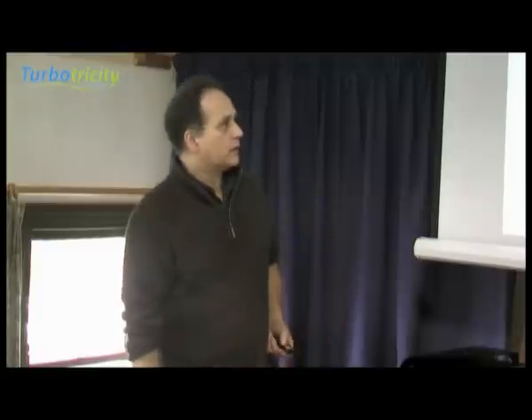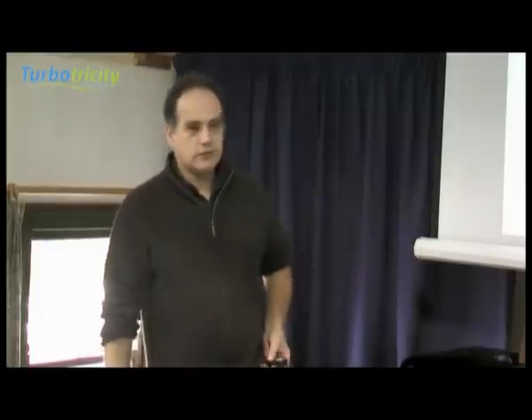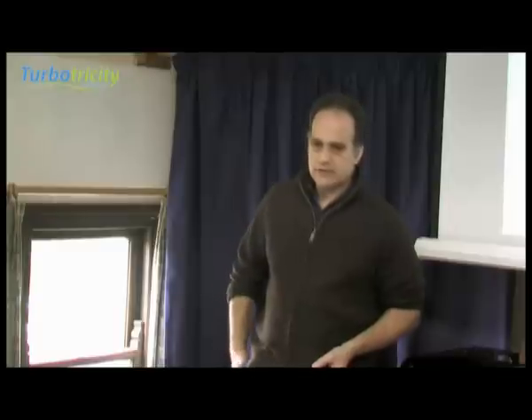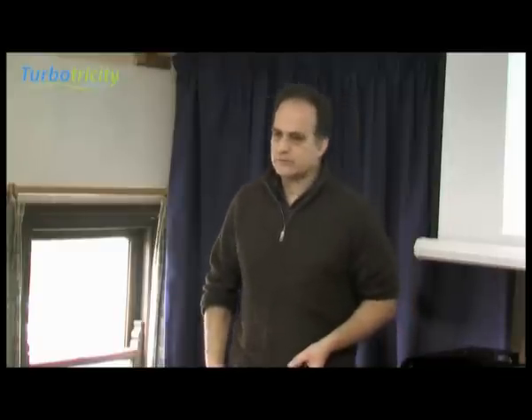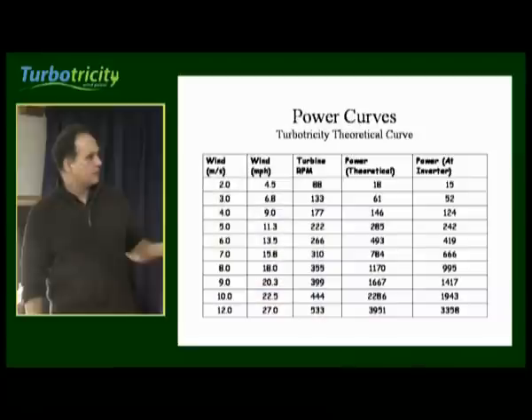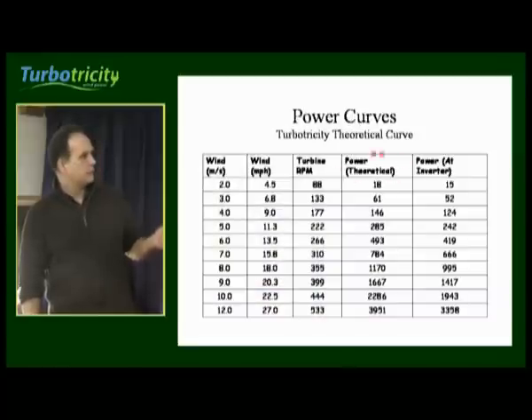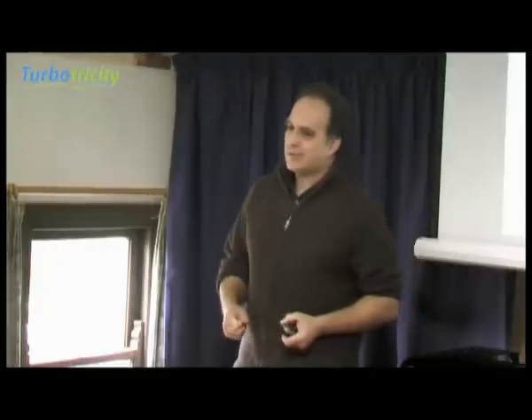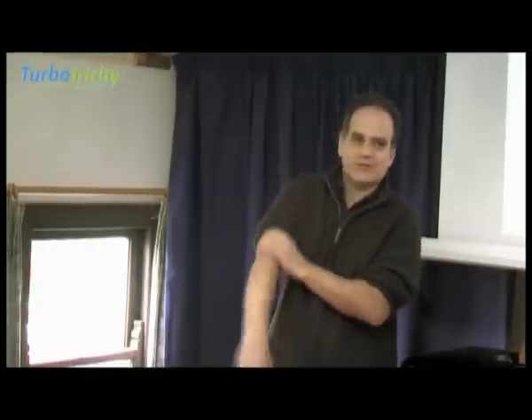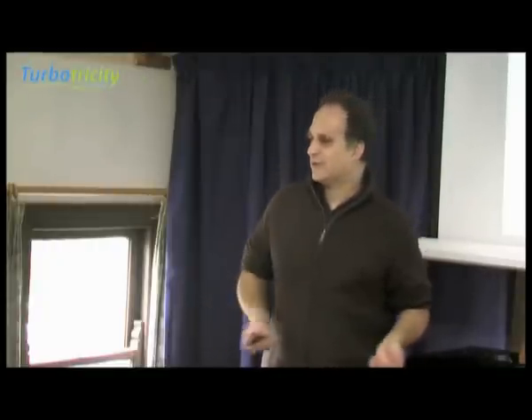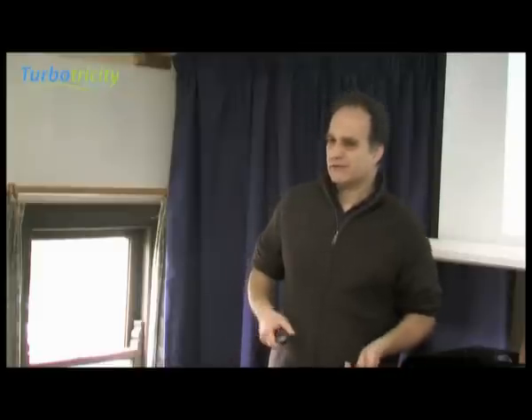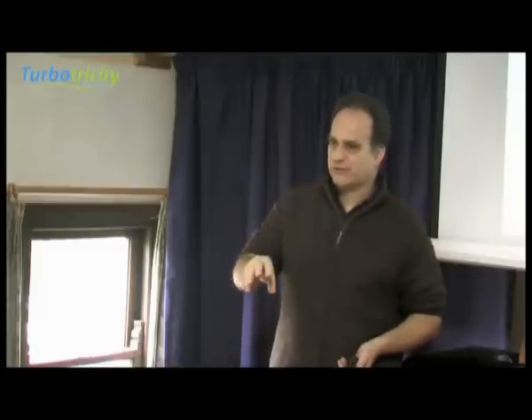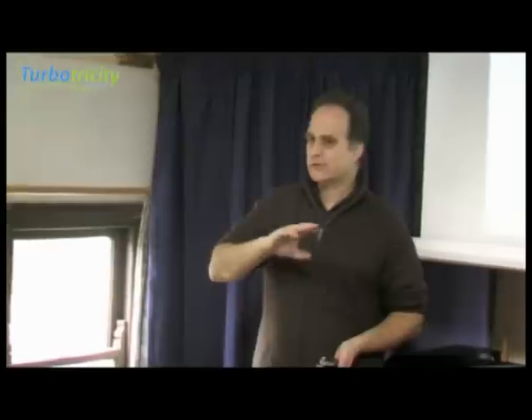You get a power curve from your turbine. At the moment, in relation to our own turbine, we're still using theoretical power curves — we have done trials and we're getting close to it. The figure you want is what the output is at the other end of the inverter. Some people will tell you what's coming out of the generator, but that's not what you're actually getting. What you're getting is when that power has gone through the rectifiers, through the controller, through the cable from the turbine to the house, through the inverter — what are you getting out of the inverter into your meter? That's the figure you want.